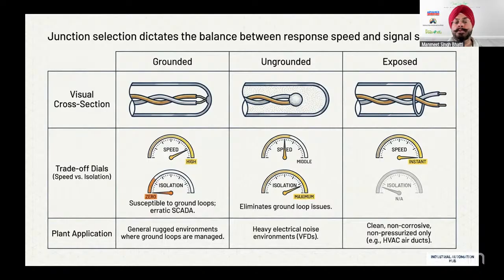So this kind of thermocouple should be used where you have a high level of electrical noise. If you have very big motors in the picture, very big VFDs over there, the thermocouple design should be ungrounded. We should not go for a grounded one, but for an ungrounded one. Because when you have so many heavy motors and heavy loads running around, it's very difficult to find a perfect ground or perfect earth. There is a possibility that you are using the same cable, so there is lots and lots of noise coming up. So whenever you are installing it in a very noisy environment where you have VFDs, big capacitor banks, big motors, make sure that you go for the ungrounded one.